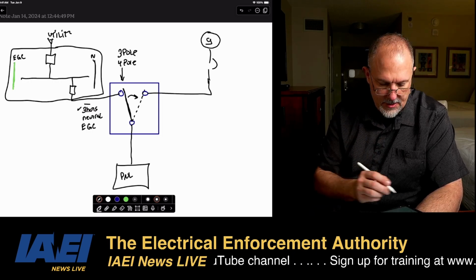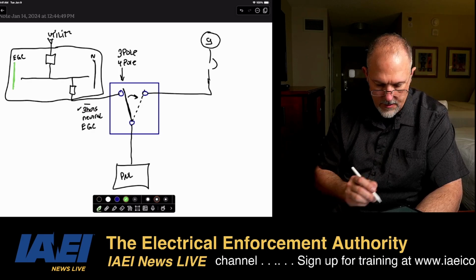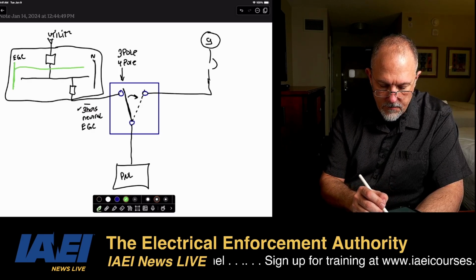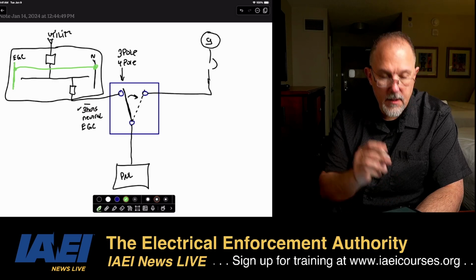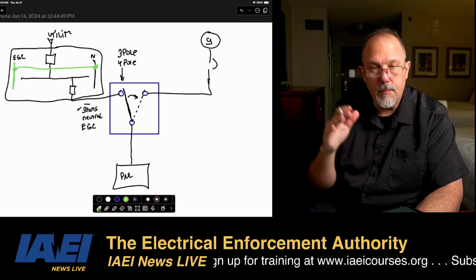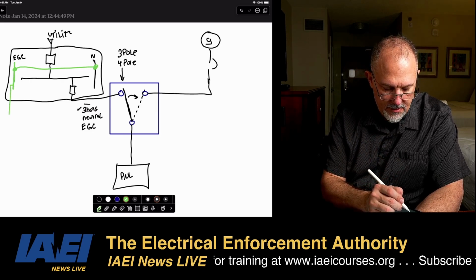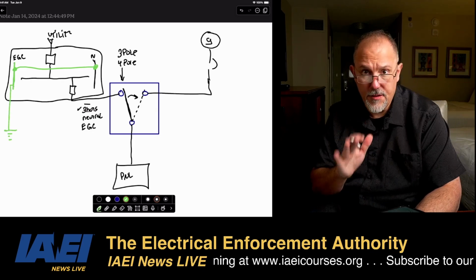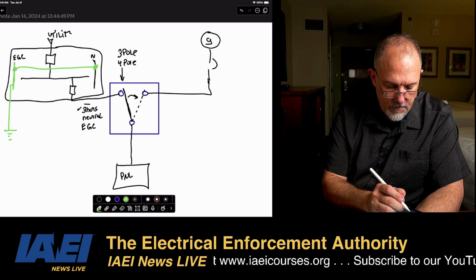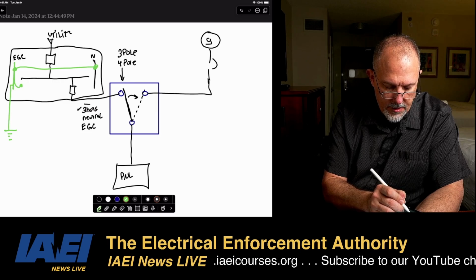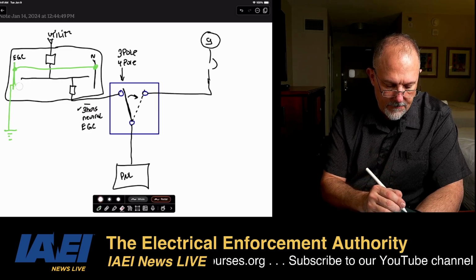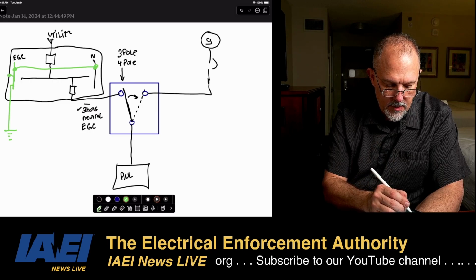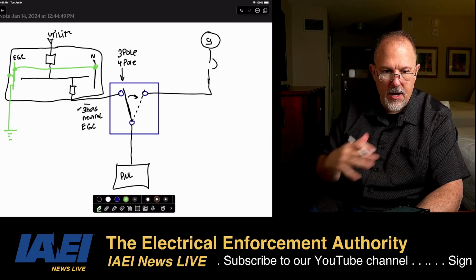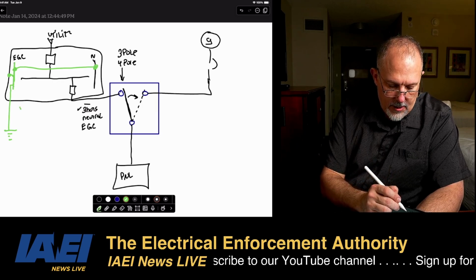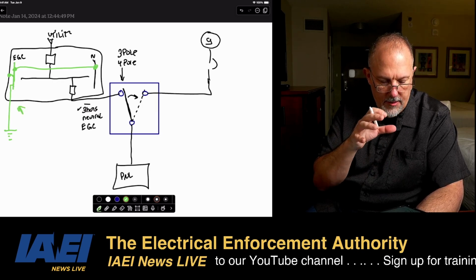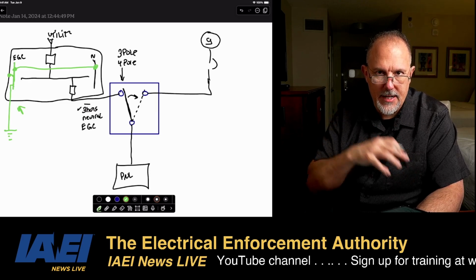Now, off of this, I will make sure that I bond these two together in my service equipment. I'm bonding the neutral and the equipment grounding, and I come off of this and go to the earth, and then I also bond my equipment. Let's do it this way. I'll show it to the outside of the box. So I have all of this going on here. My neutral and my equipment grounding, everything is bonded and combined together.